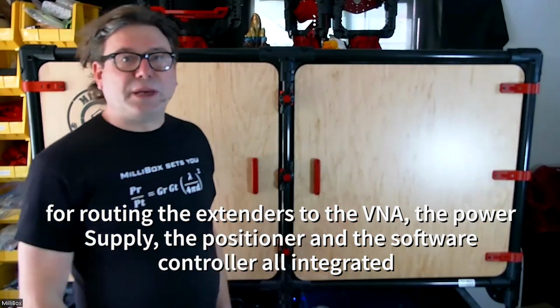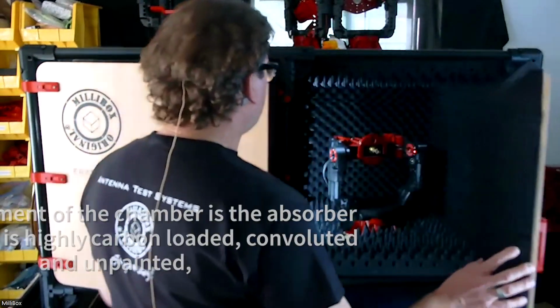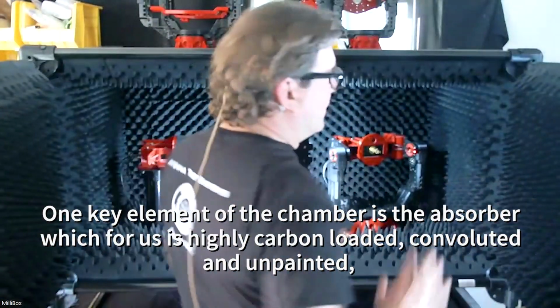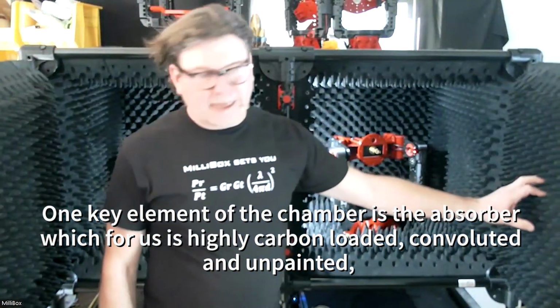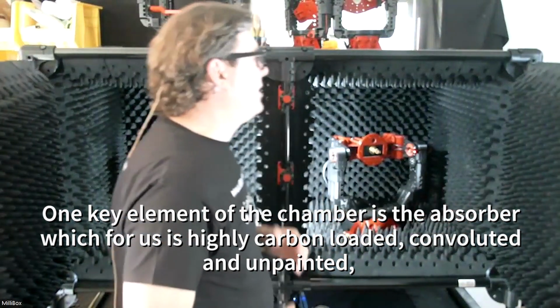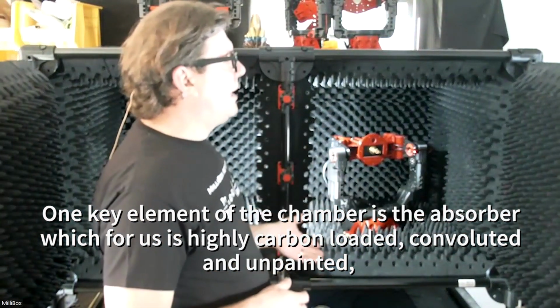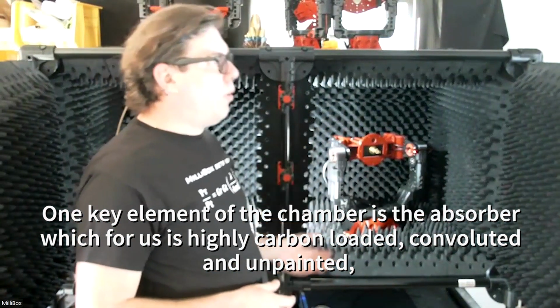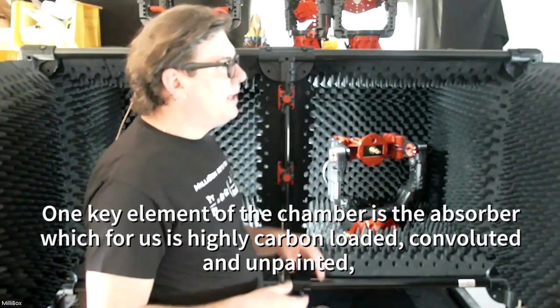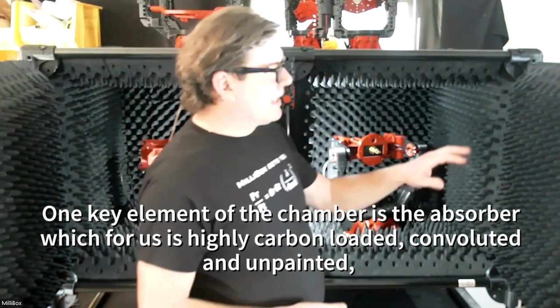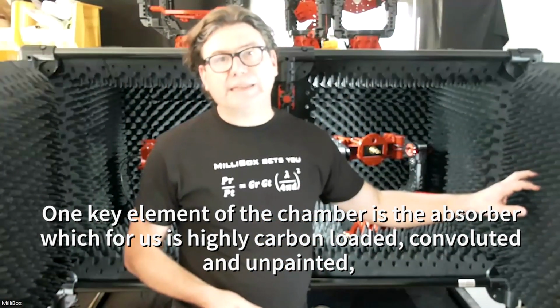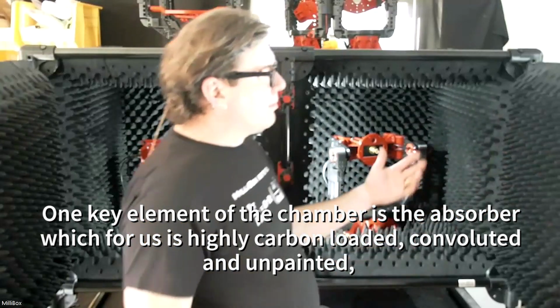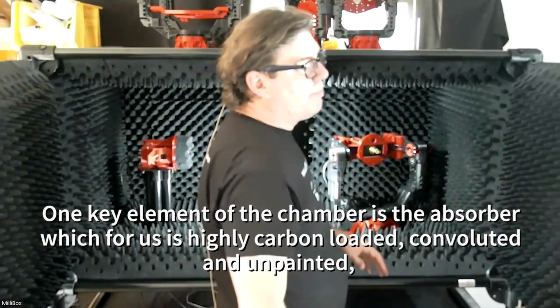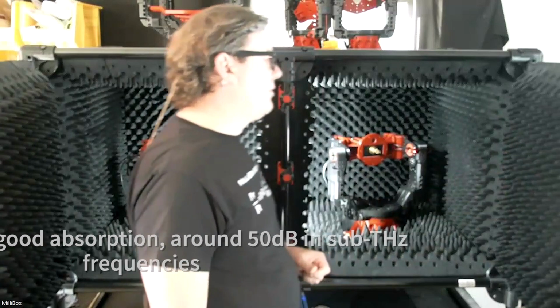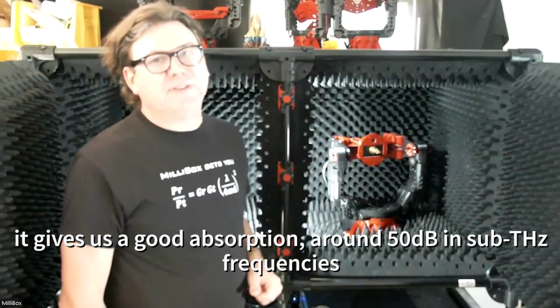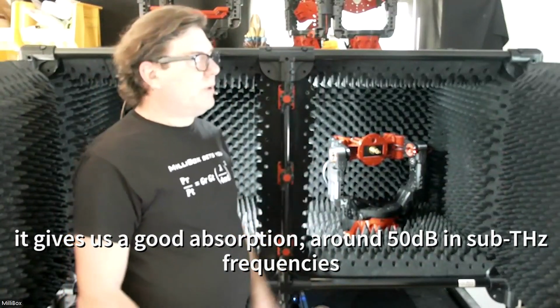All right, so let's take a peek on the inside. Inside, of course, a key element is the absorber. The absorber that we have is performing very well in sub-THz frequencies. For one, it's convoluted and not pyramidal, and that's something that we like for those kinds of frequencies, and especially it's non-painted. We like blue, we like orange, but we don't like paint on our absorber for those frequencies. So it's still performing at 50 dB attenuation all the way in sub-THz.